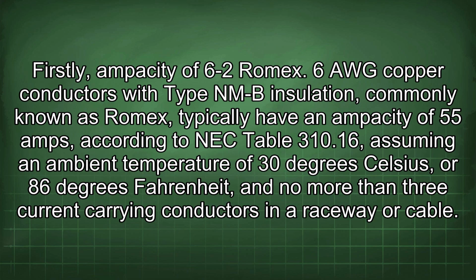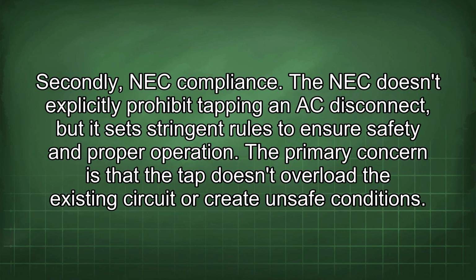6 AWG copper conductors with type NMB insulation, commonly known as Romex, typically have an ampacity of 55 amps, according to NEC table 310.16, assuming an ambient temperature of 30 degrees Celsius or 86 degrees Fahrenheit, and no more than 3 current carrying conductors in a raceway or cable. Secondly, NEC compliance. The NEC doesn't explicitly prohibit tapping an AC disconnect, but it sets stringent rules to ensure safety and proper operation. The primary concern is that the tap doesn't overload the existing circuit or create unsafe conditions.